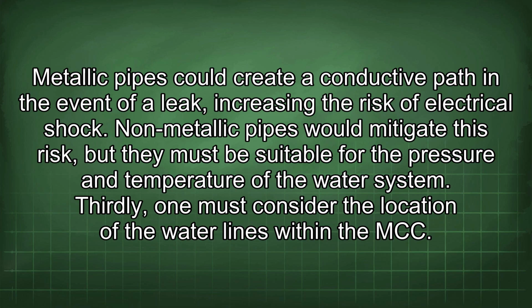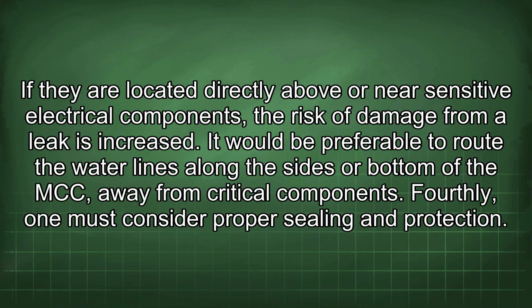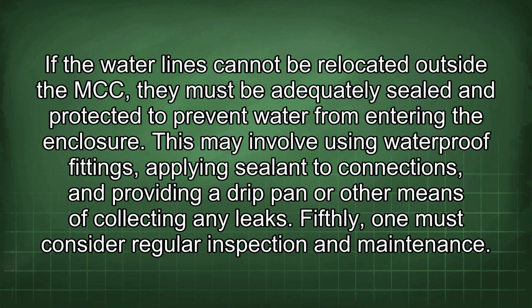Thirdly, one must consider the location of the water lines within the MCC. If they are located directly above or near sensitive electrical components, the risk of damage from a leak is increased. It would be preferable to route the water lines along the sides or bottom of the MCC, away from critical components. Fourthly, one must consider proper sealing and protection. If the water lines cannot be relocated outside the MCC, they must be adequately sealed and protected to prevent water from entering the enclosure. This may involve using waterproof fittings, applying sealant to connections, and providing a drip pan or other means of collecting any leaks.